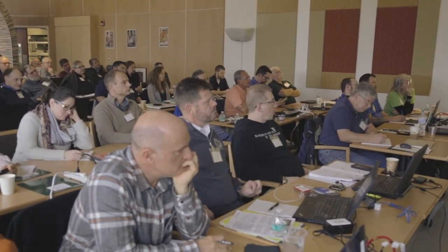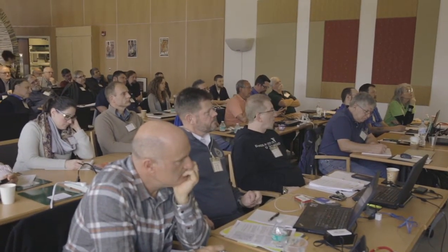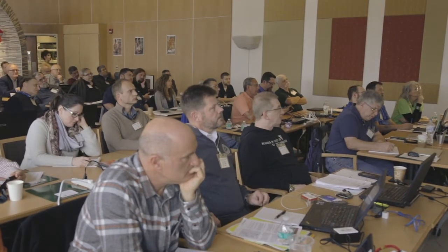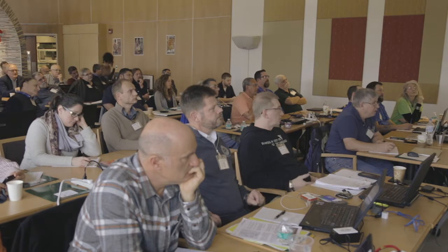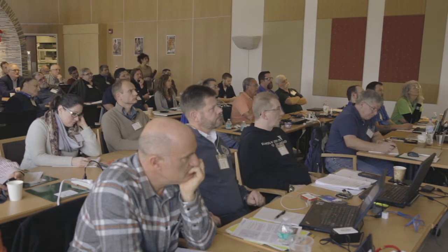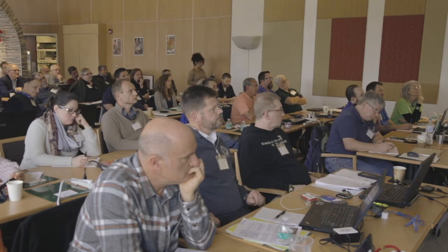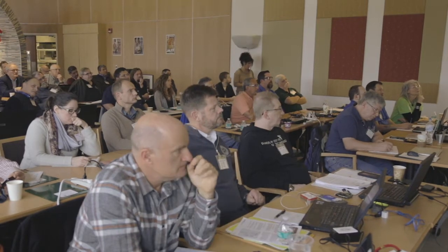And ultimately, what are we trying to maintain? Are we trying to maintain, assuming a fixed set point, are there multiple places in this system we're trying to maintain a temperature? Or is there one point where we have a temperature we want? One point. Yeah, we want the temperature coming back to the chillers to be the right number, and we want to with that temperature right there in that pipe. Well, if I control off of that temperature, now I have that lag problem, right?